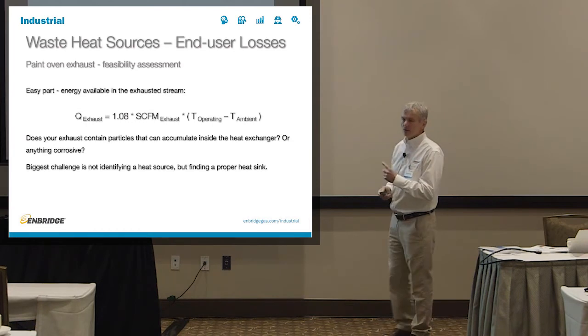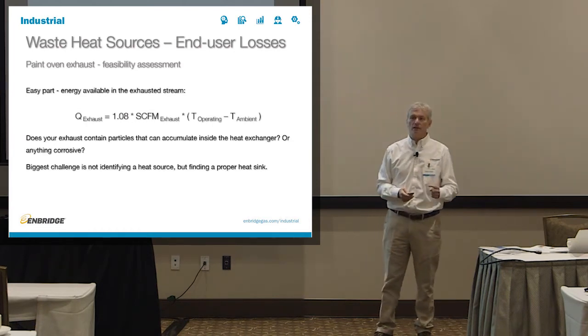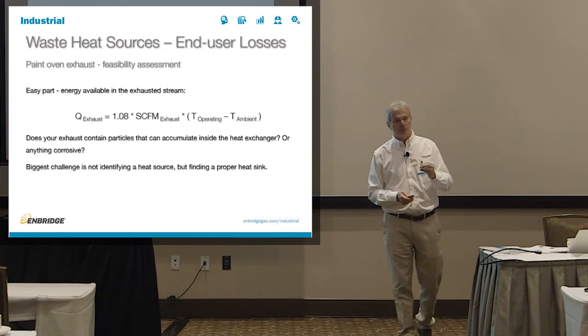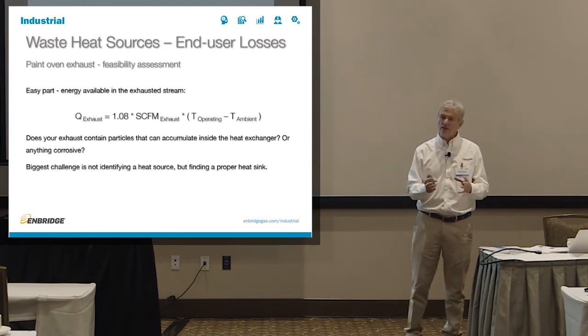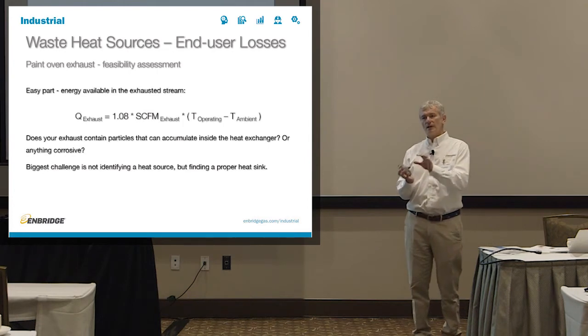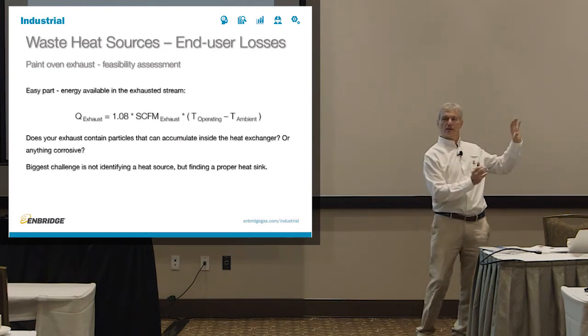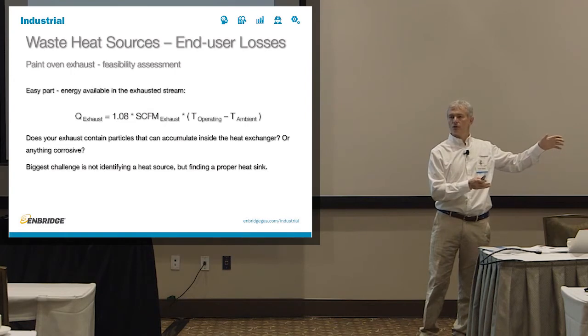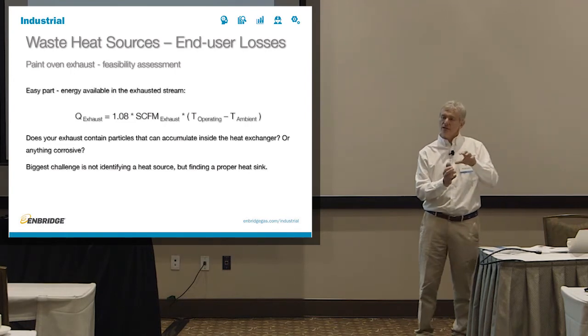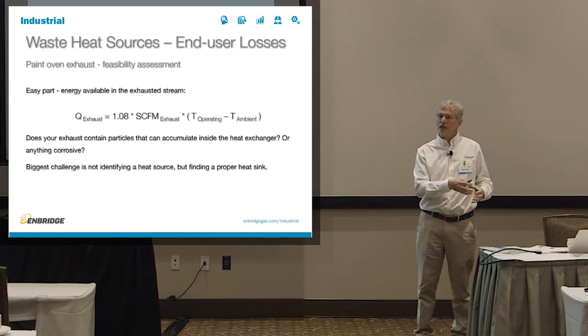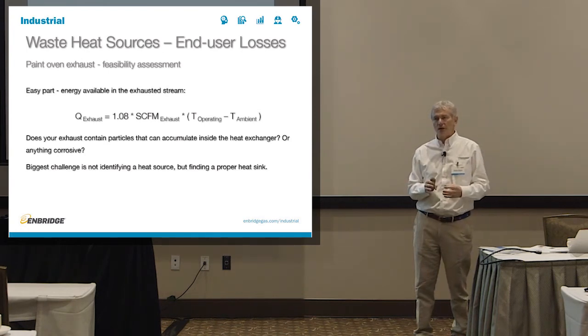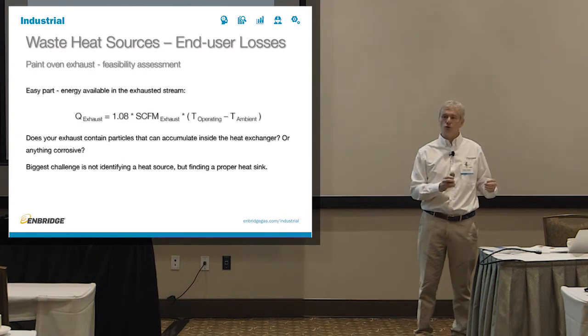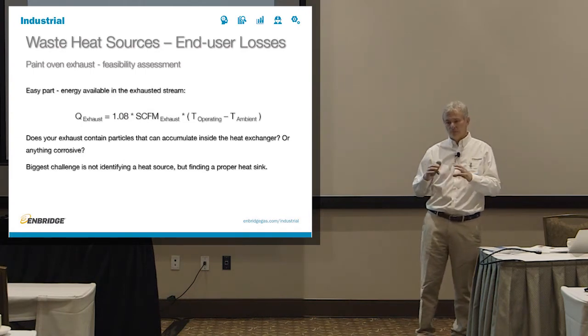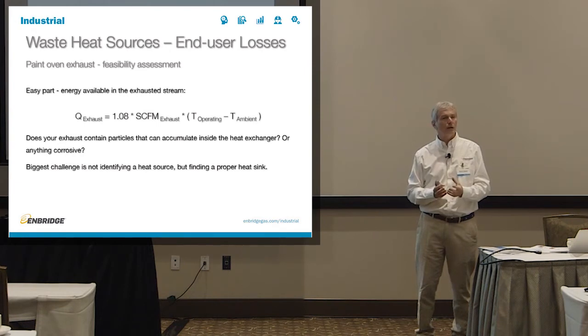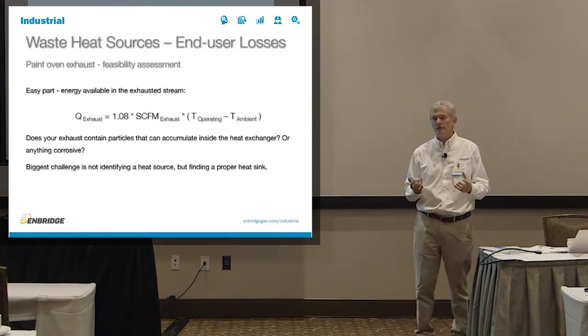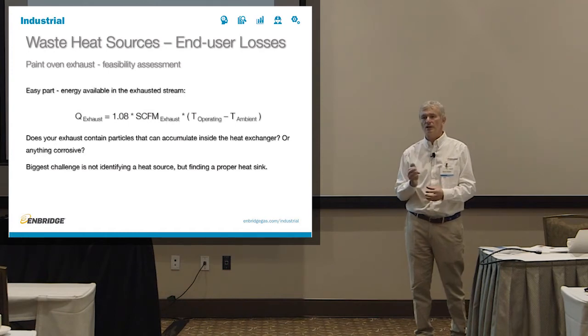The other thing is, the biggest problem is finding a good heat sink. That's important to understand because it's 300 degrees F, let's say, at the exhaust. If you're going to take that exhaust and put it into a pipe and take it 300 feet away, you're going to lose a lot of energy. So you want to use that heat either directly in the same oven that you're taking it out of or somewhere very close by. Ideally, again, you want to use it for process. If you use it for the heating load of your facility, you'll only use 40 to 60% of it, which increases your paybacks.